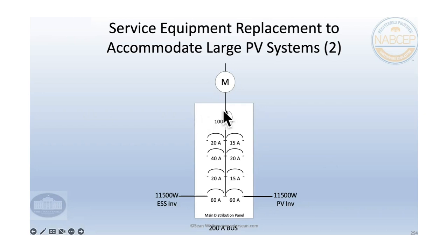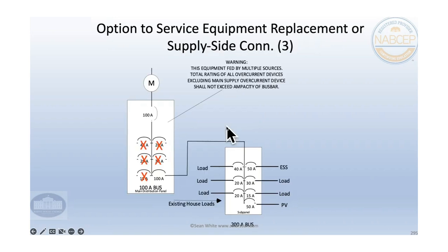And if you don't like pulling out the panel board and reinstalling a new one and whatever kind of requirements there's going to be for that, what you can do here is you can bypass this panel board, which I think is kind of a real neat creative one. So we're using this sum rule, the sum of the breakers rule. We take all the loads out, we stick them on a sub panel. There's a 100 amp, we're going to a 200 amp panel. We feed it with a 100 amp breaker. We don't have to touch any of this stuff. And then all of a sudden we've got all kinds of options there.